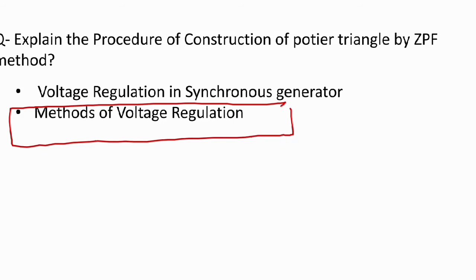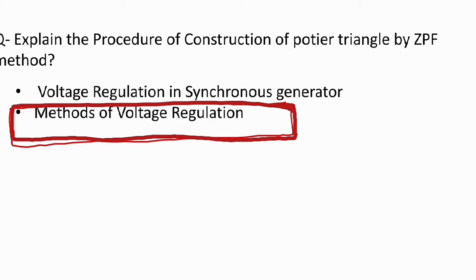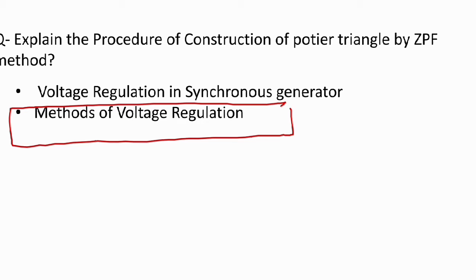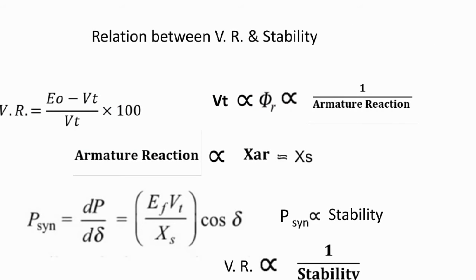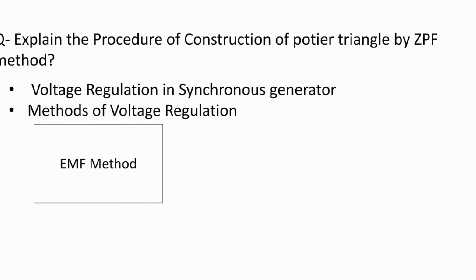Now, methods of voltage regulation: there are generally four methods. The first is the EMF method. This is the pessimistic voltage regulation method — we get voltage regulation higher than the actual value. The reason it is pessimistic is that it considers all reactances as leakage reactances.